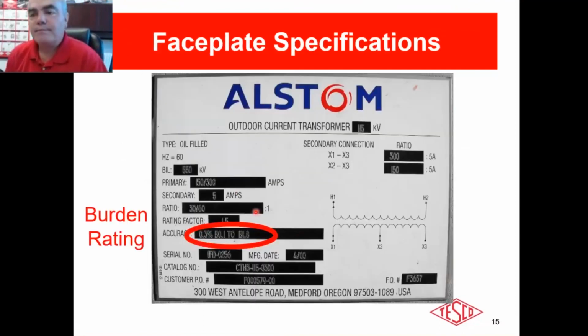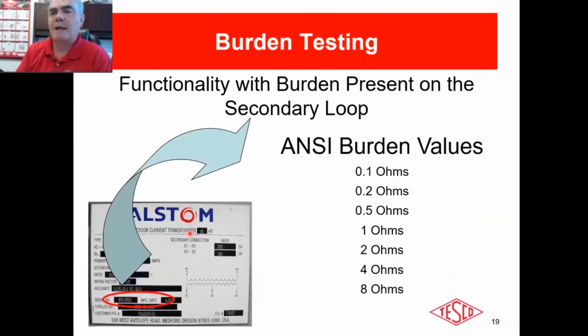All right. So the accuracy is actually an accuracy and a burden rating. In this particular case, I don't know if you can see it, but it says it's 0.3% between these burdens, starting at 0.1 and going up. Okay, it means if I get too much of a burden, I'm going to lose accuracy. All right, it says 0.3% accuracy. So I'm going to come back to that slide in just a second.